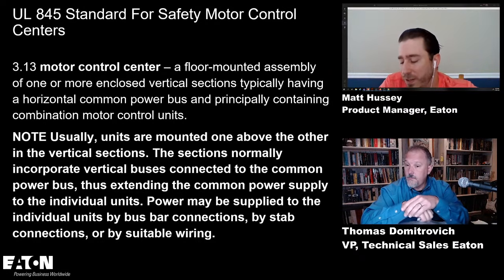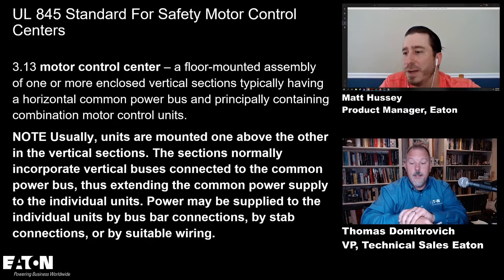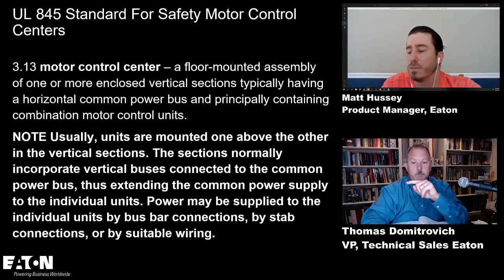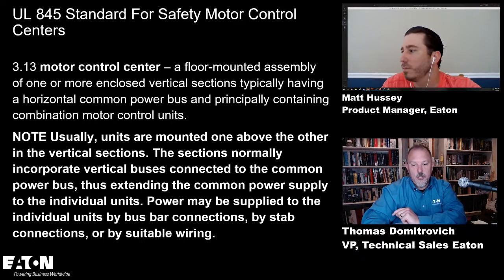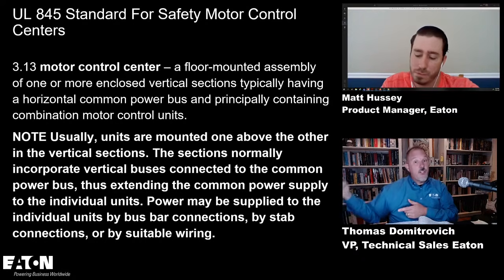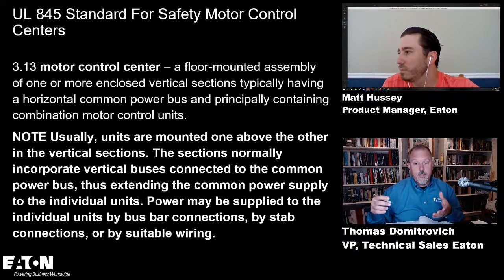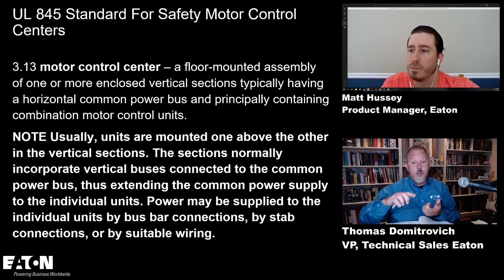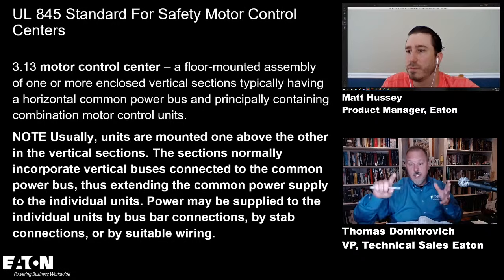Yeah. That's what we were talking about a little bit before with the arc resistant application. Right. So it could either be back to back for 2 different incoming feeds, or a common shared bus between the 2 as well. Okay. And I could have sworn I saw the word principally in here too. Typically having a horizontal power bus, and principally containing combination motor control units. So to your point earlier, we can put other things in there, because outside of just combination motor control units, we saw meters and circuit breakers in there, all these other different things.